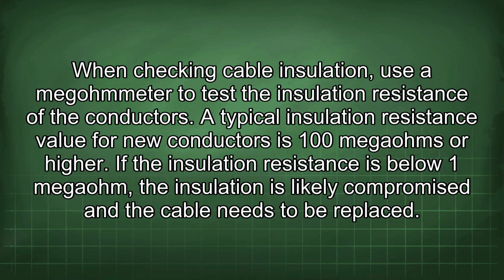When checking cable insulation, use a megohmmeter to test the insulation resistance of the conductors. A typical insulation resistance value for new conductors is 100 megaohms or higher. If the insulation resistance is below 1 megaohm, the insulation is likely compromised and the cable needs to be replaced.